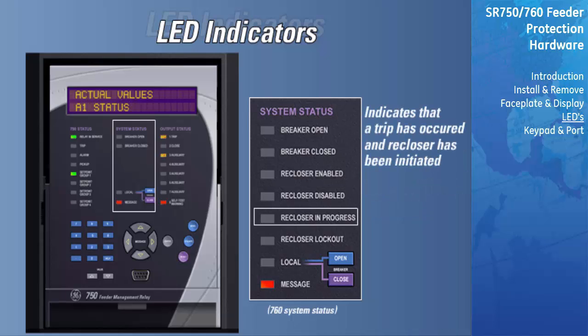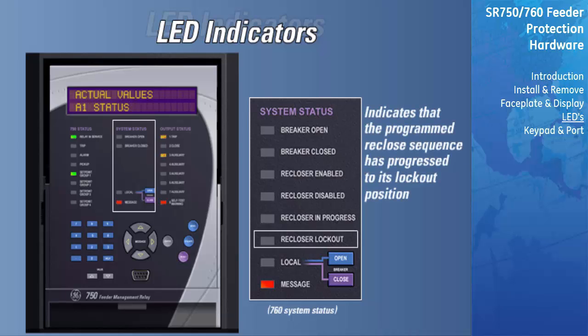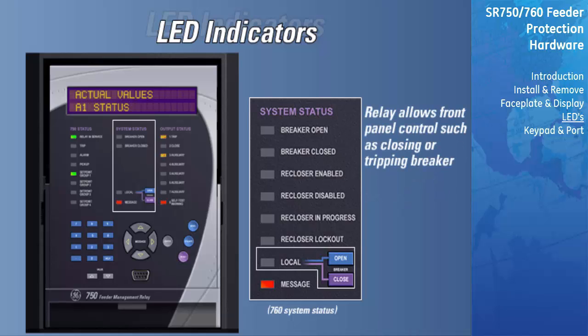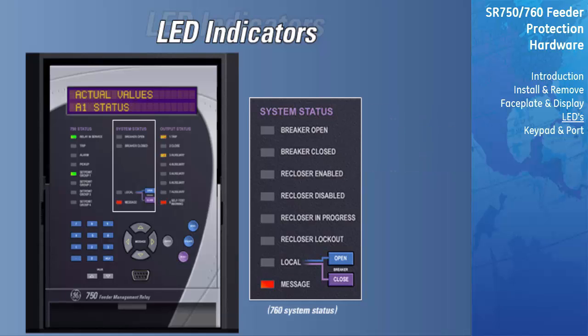The Recloser in Progress LED will illuminate when a trip has occurred and reclosure has been initiated. The Recloser Lockout LED will illuminate when the programmed reclose sequence has progressed to its lockout condition. The Local LED indicates when the local mode has been assigned to an asserted contact input, allowing the breaker to be opened and closed using the front keypad. The Message LED will indicate when there is a trip or alarm message present in the relay. If there is more than one message, using the Next button will scroll through the messages.